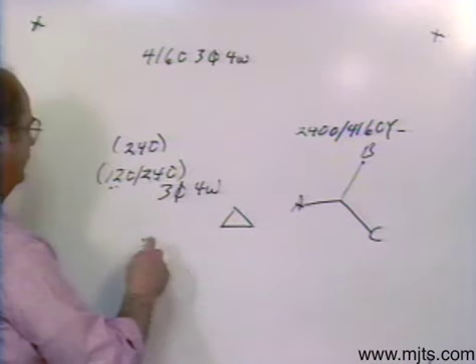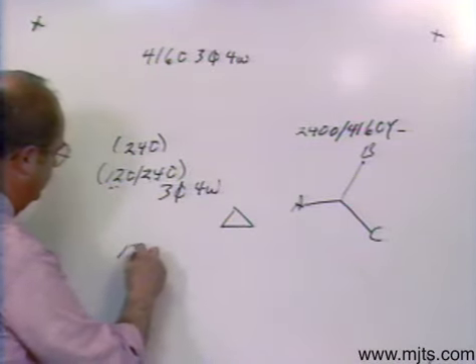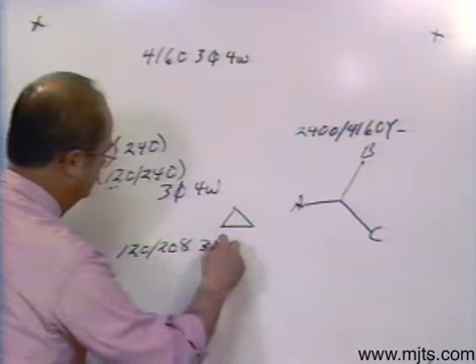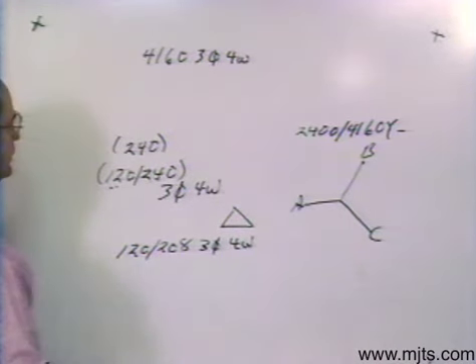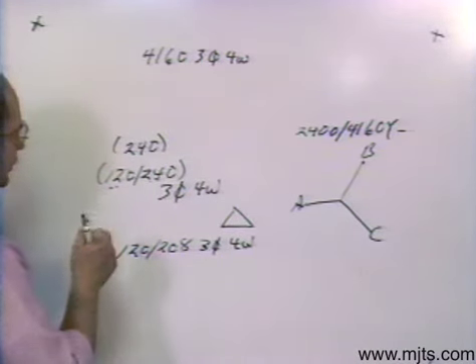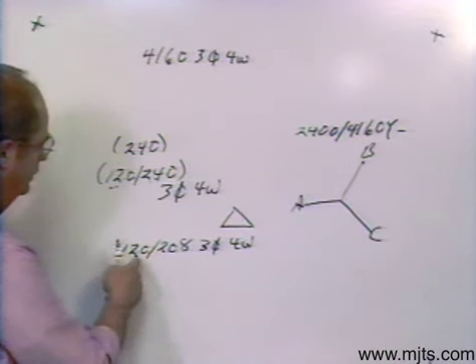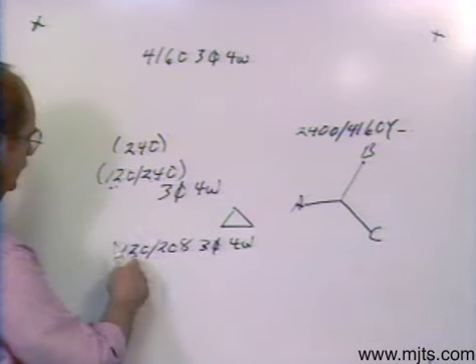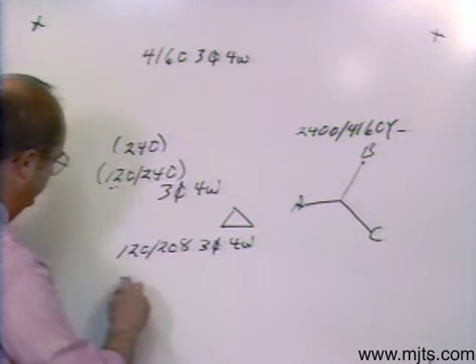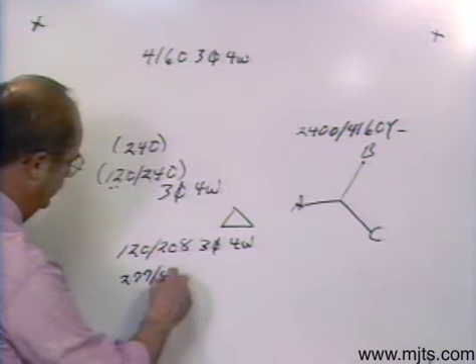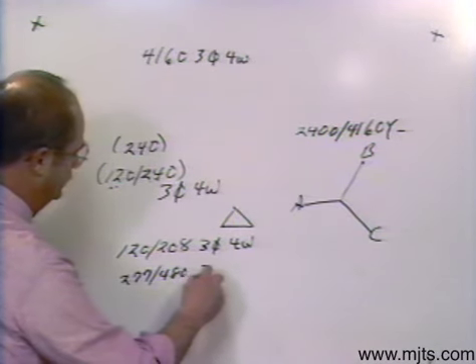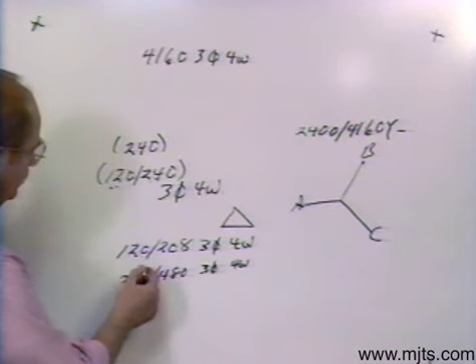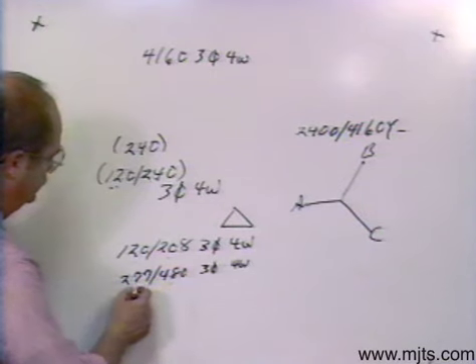On the other hand, if I have numbers that look like this — 120/208, 3-phase, 4-wire — you see we have a 1-to-1.73 relationship. Another example of that would be 277/480, 3-phase, 4-wire. There again, 1 to 1.73. If I wanted this rating, I know that I'm going to have a Y connection on the low side.